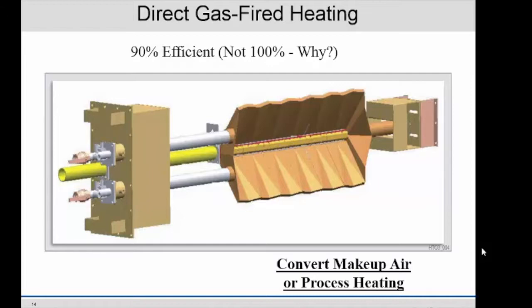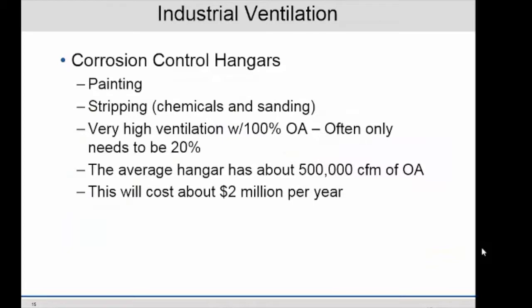But if it's a facility like a painting facility where they need the humidity, it's a benefit to have that. So you'll get a certain amount of humidification out of a direct gas fired on a painting facility. Corrosion control hangars, they're really big energy consumers. They do these planes that are as big as a 777, huge planes they do at these military bases. And they're always 100% outside air because they're older designs. You only need to be 20%. As far as the commercial industry, it allows 20%. And the Air Force and Army have done some hangars at 20%, so that's a big energy saving opportunity.